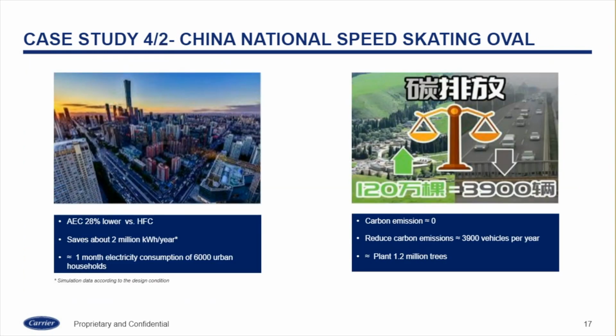This is a simulation of the system impact of the CO2 unit. We simulated the annual energy consumption of the CO2 system compared with HFC. The CO2 system has about 28% energy saving over the whole year of operation, and it saves about 2 million kilowatt-hours of electricity for the whole year. If we count household consumption, it's about 6,000 urban households in Beijing for 1 month's consumption. So this is a significant energy saving.